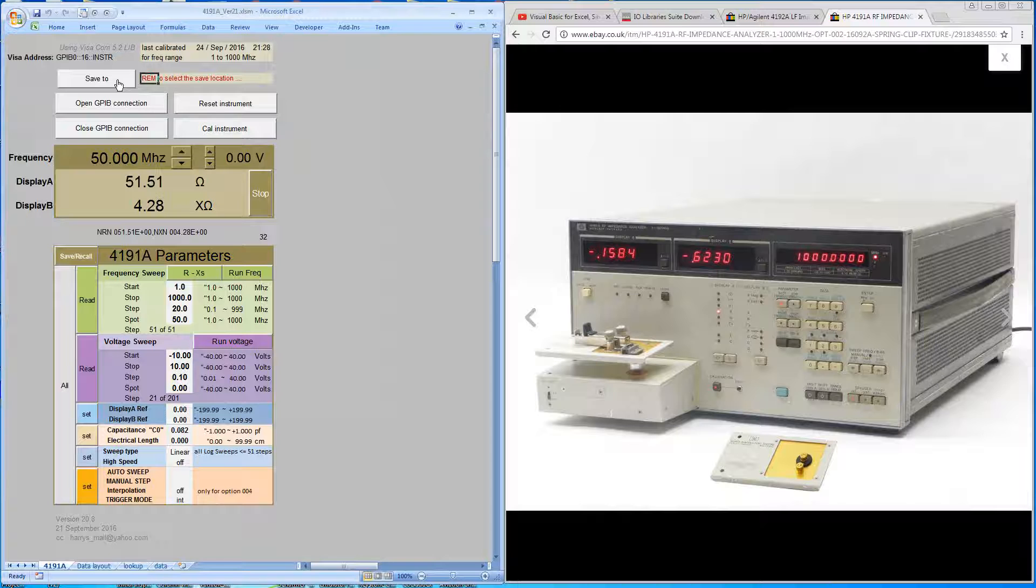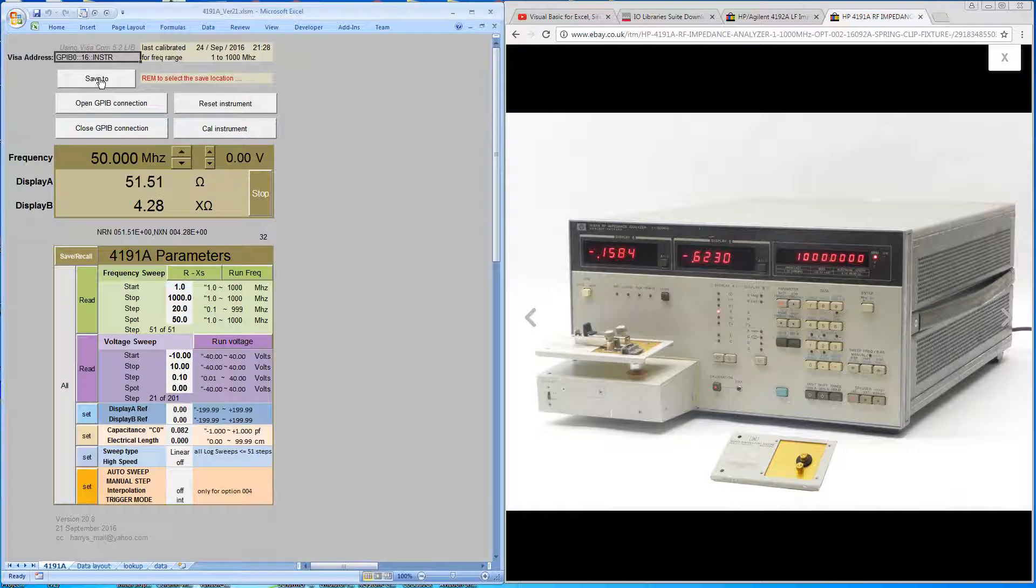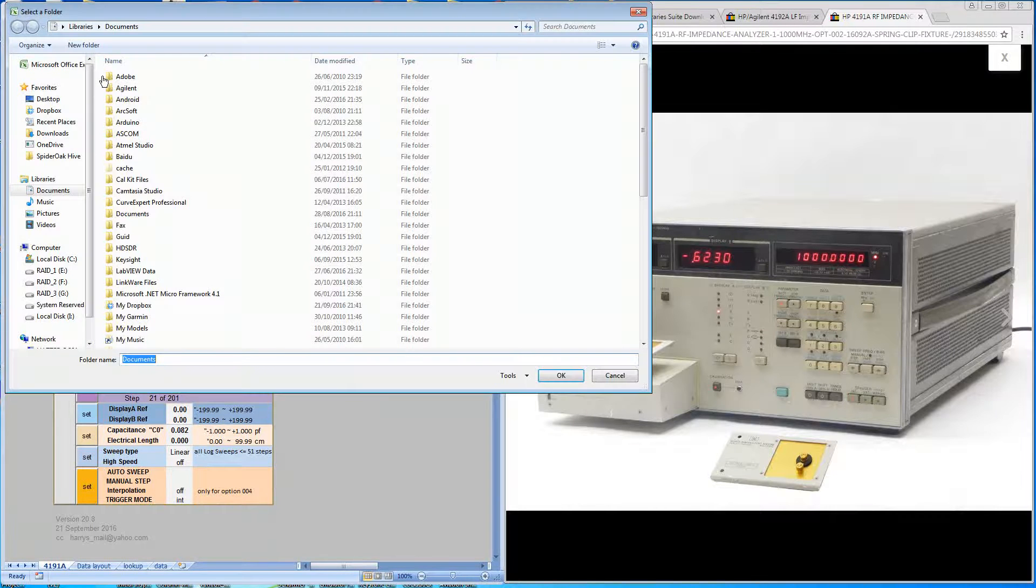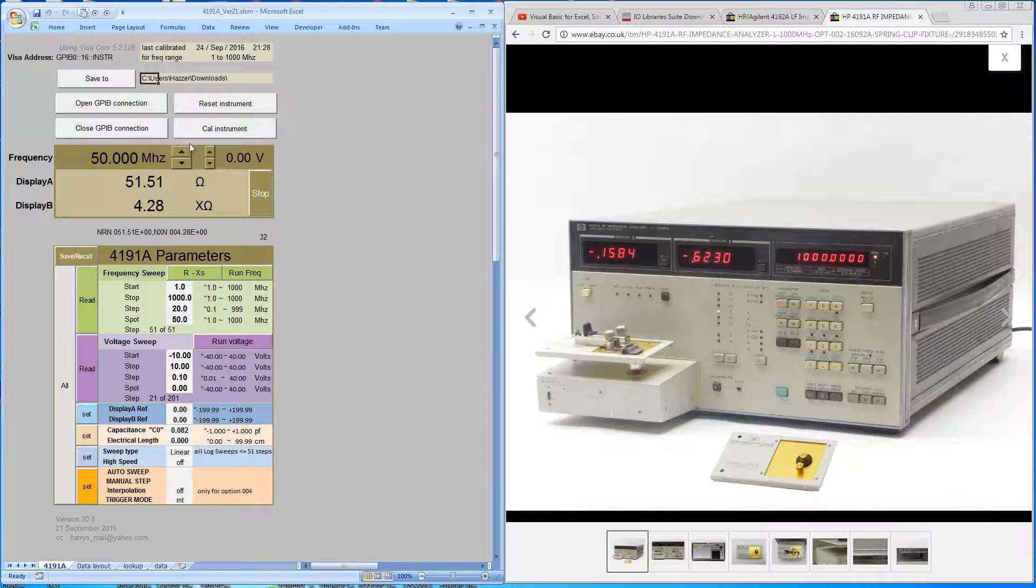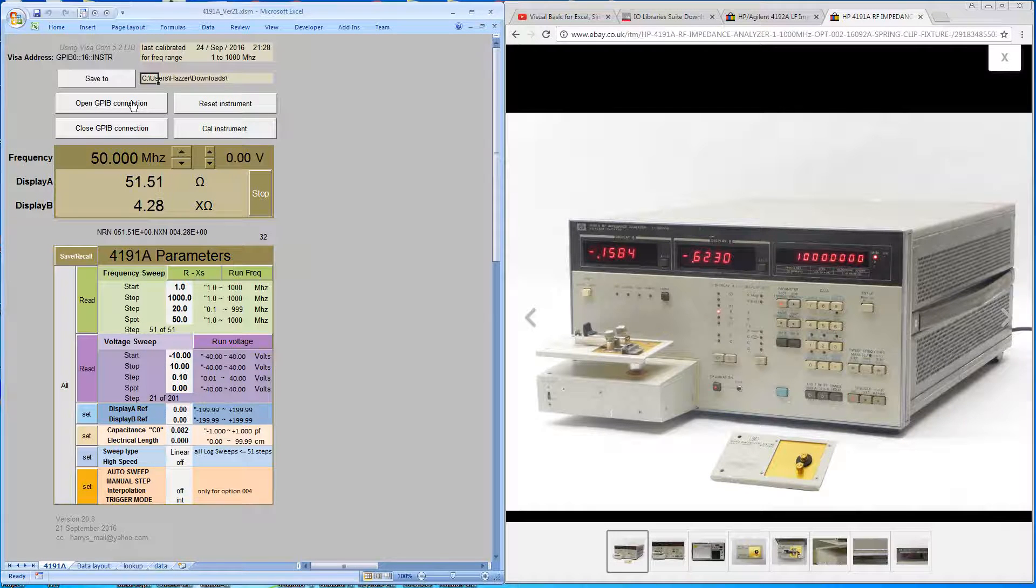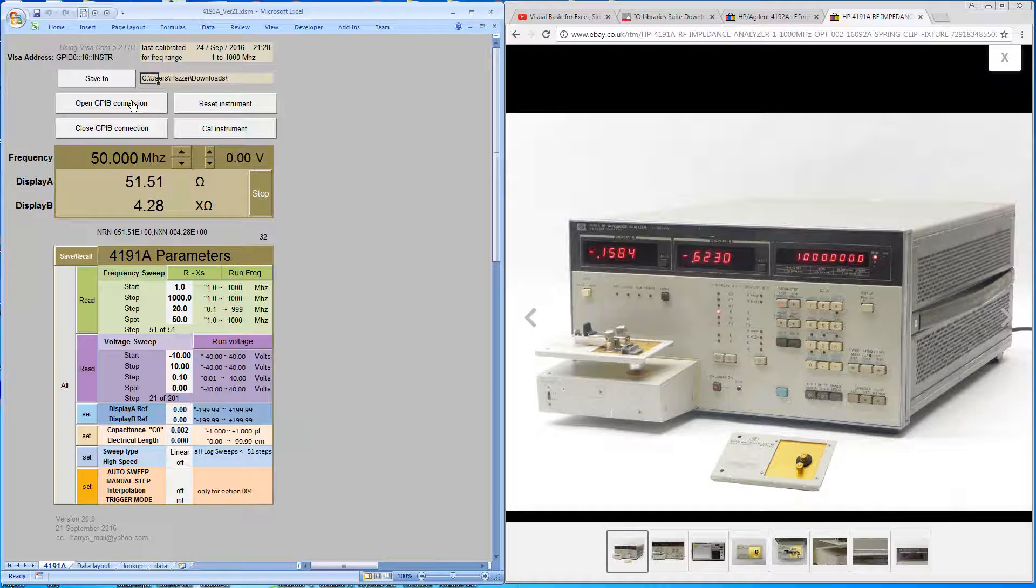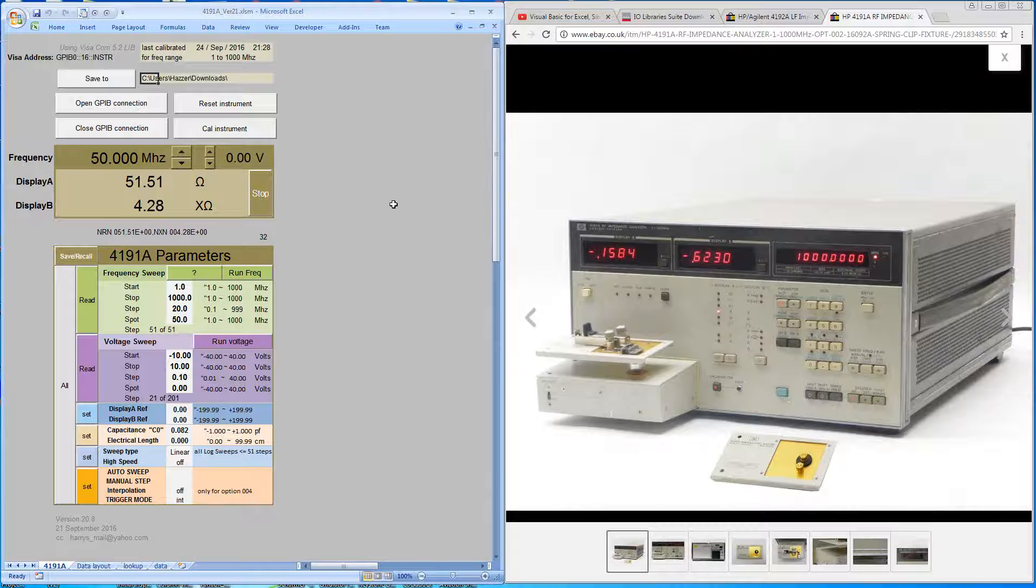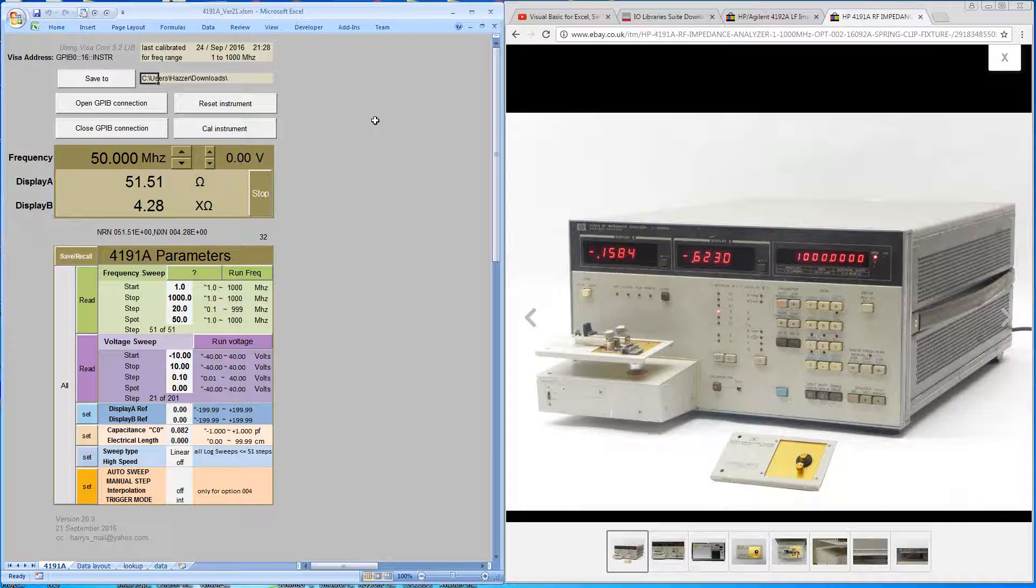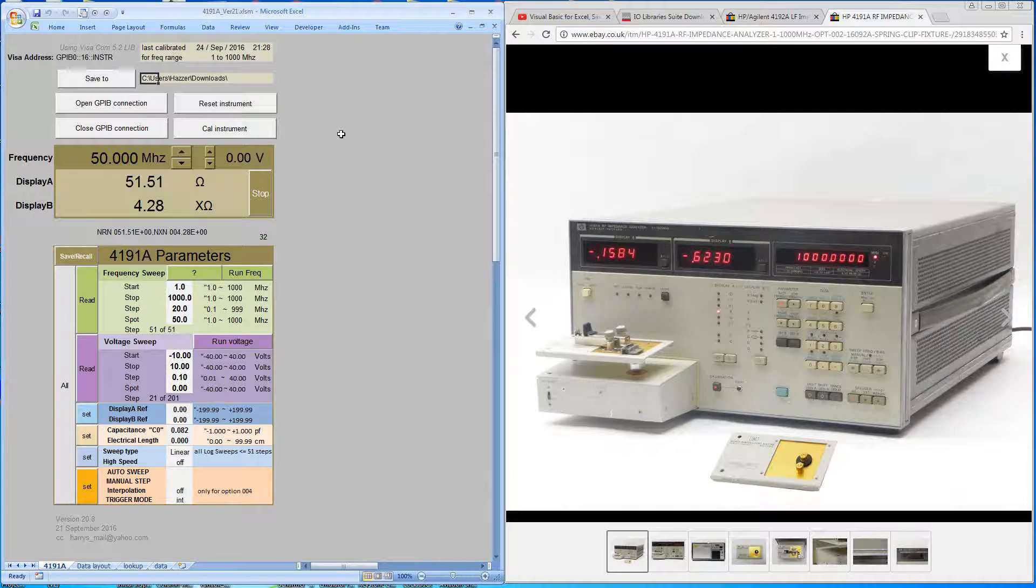First thing you need to do is provide the instrument address. In my occasion it's address 16. You're then asked to provide a save location. I'll use the download folder. Next thing you're asked to do is to open the connection to the machine. So my machine is connected over the GPIB bus to this computer. So we'll open the connection, open GPIB. I've added some audio annotation to the code so it just lets you follow along. Since we've just connected to the machine it would be sensible to do a reset, just to return the machine to its default condition.